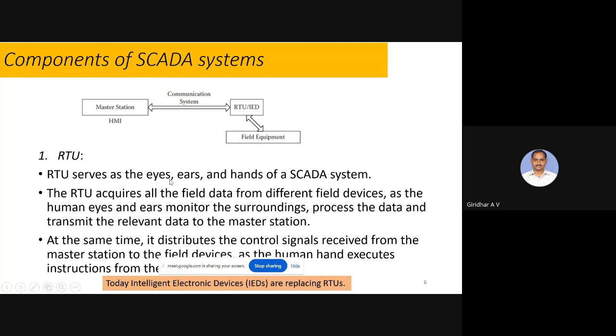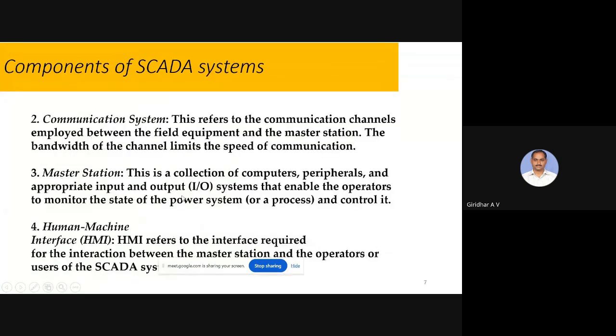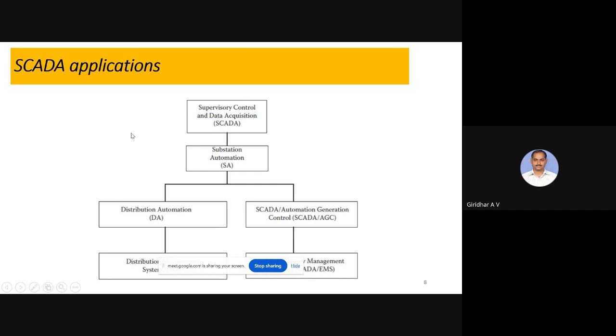So here the RTU holds the main role in monitoring and controlling the devices. In the SCADA system, there is the communication system and the master stations, with the human machine interface, like displays, at the SCADA master station. The whole bus system will be monitored, and wherever required, control or protection can also be done. So these are the typical SCADA applications we can see.